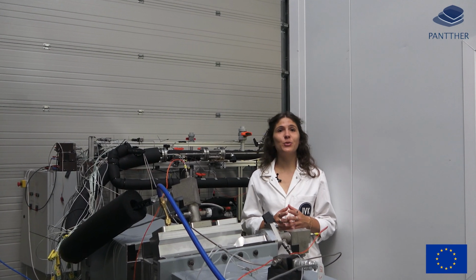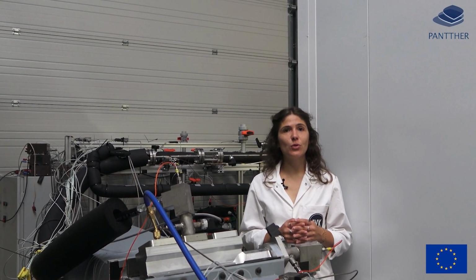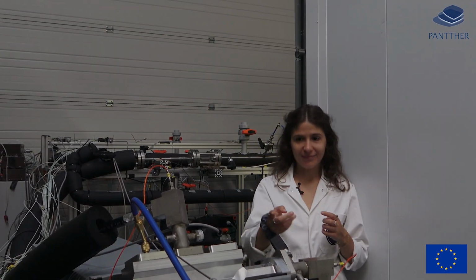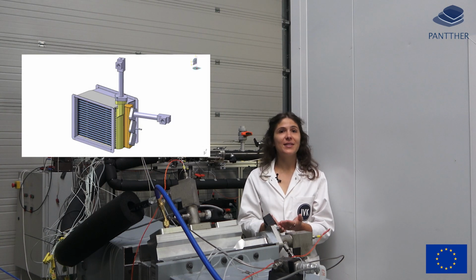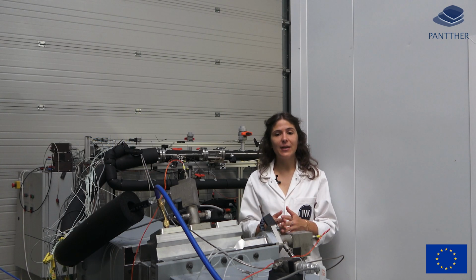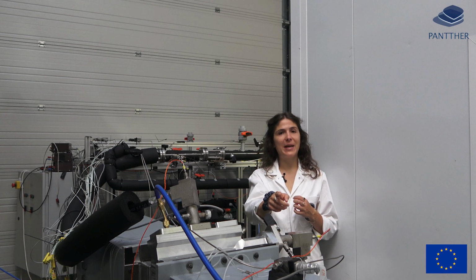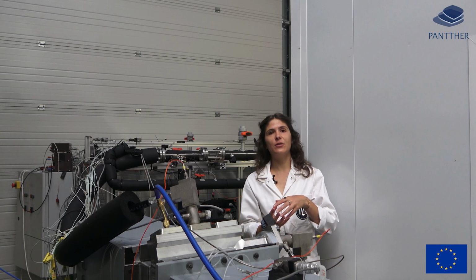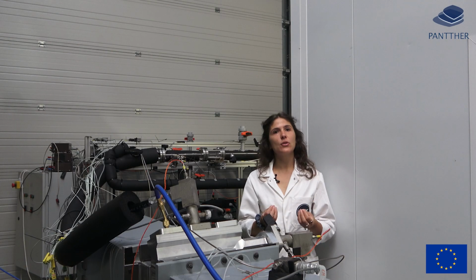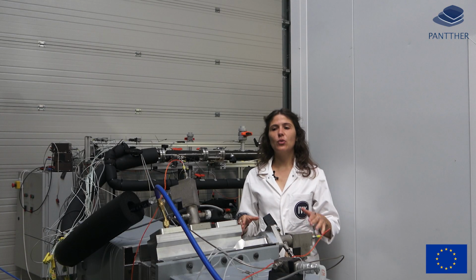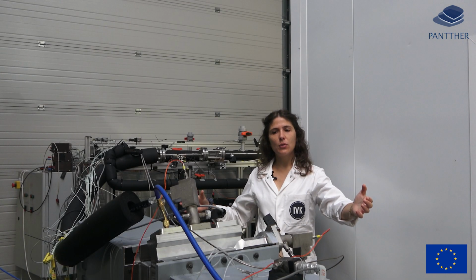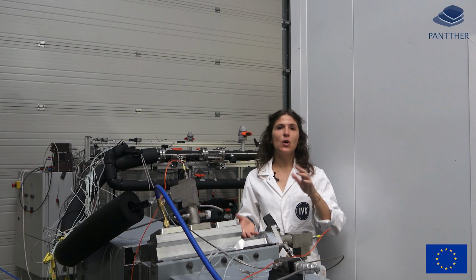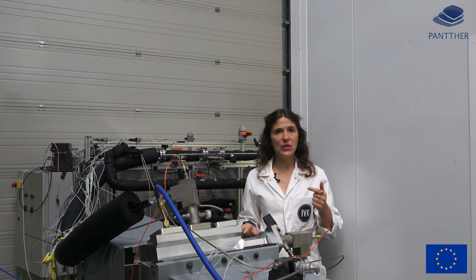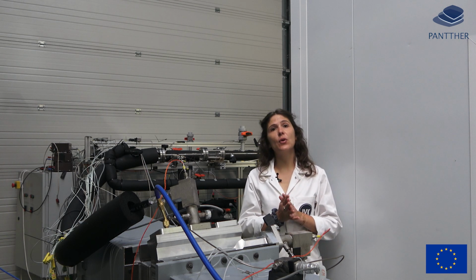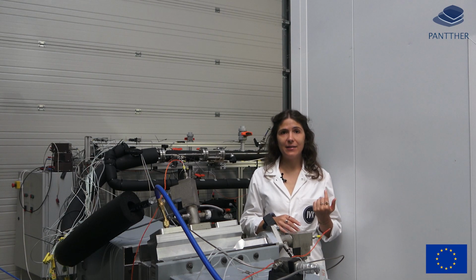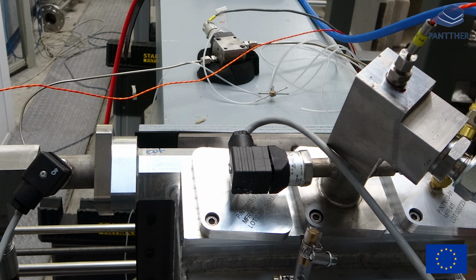The final step of the project was to test this refrigerant in true and real evaporators that you can see here. So it's an evaporator that is actually used, but that we simply a bit modified. So we increased the inlet pipe diameter to allow for more stratified flow pattern, so to be in the worst condition at the inlet. So we modified it to have more inlet and outlet. The whole section can also be turned to test the change of orientation of inlet and outlet position, and to also check if the conclusions that we had in the previous adiabatic line can be also found for this evaporator.